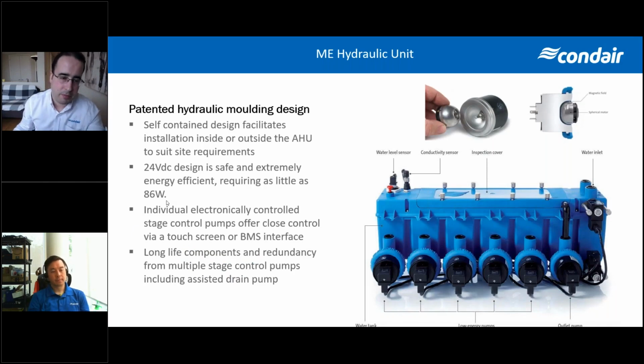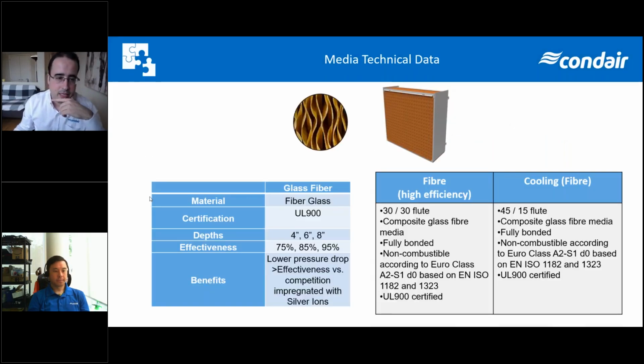We also have a conductivity sensor and a temperature sensor, for hygiene and for the water. When the water conductivity is too high, we typically drain the system and replace it with fresh water. Like I said, the media we use is glass fiber, UL 900, and the standard system is UL 998, so you can install it in a plenum or an air duct. We have 4, 6, and 8-inch media, with 75 to 95% effectiveness. Our media also has a silver coating to avoid bacterial growth. We submerge the media when we manufacture it and put the silver ion coating on. Like I said, we have 30-30 flute, a high efficiency media, and for cooling we have 45-15 media. We also sell only media to some customers; they build their own systems.